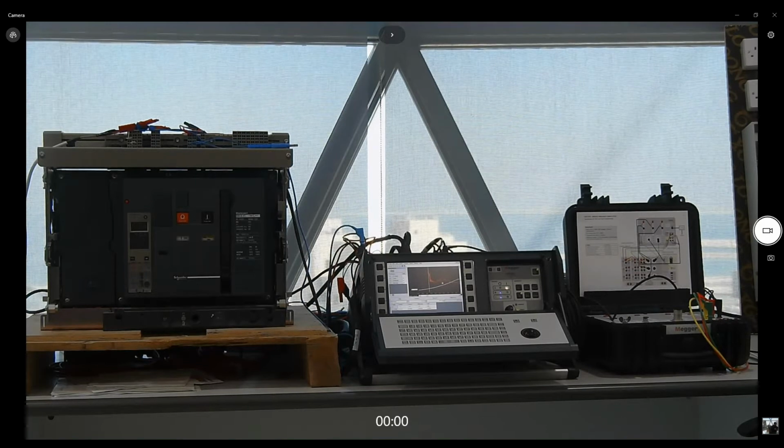But the thing that I want to mention to you is that, for example, when you are ordering a new circuit breaker, it's better to have a reference curve or a reference DRM test done at the factory before you receive that circuit breaker. So later on, when you do the test after a short circuit, you have a reference that you can compare with.